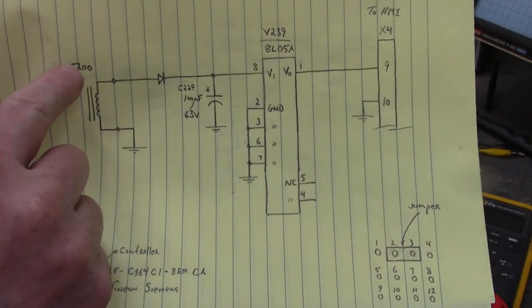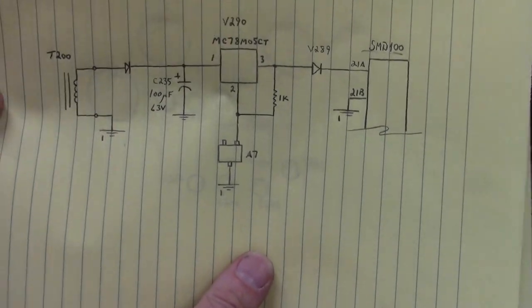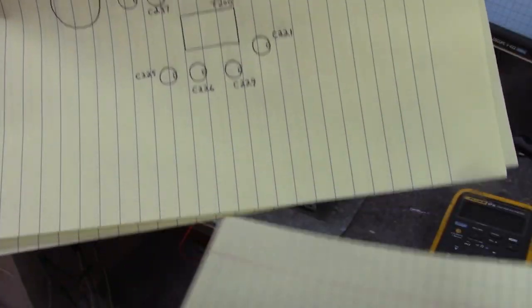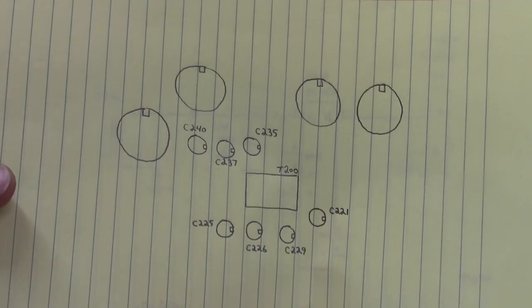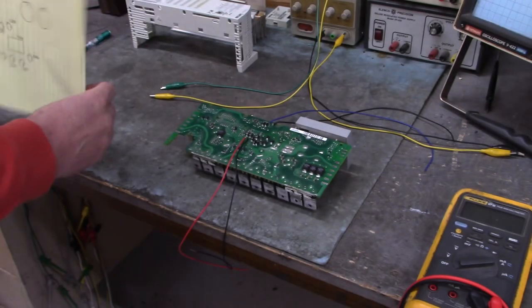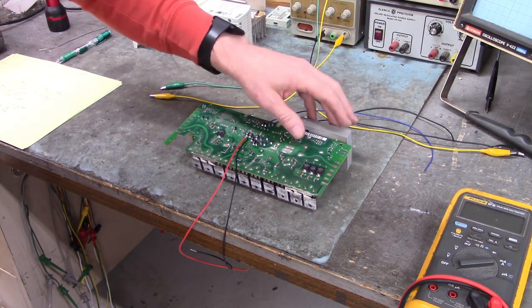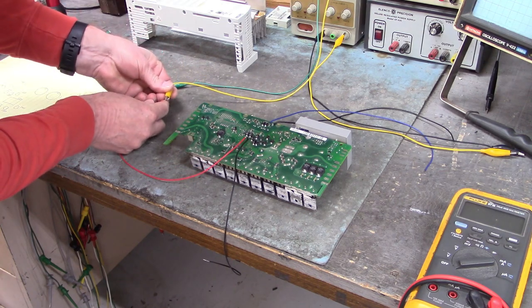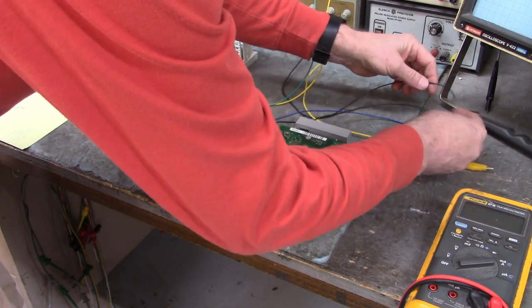I'll put my drawings up at the end of the video, but here's the circuit that powers up the panel or the lecom where we're going to pull the parameters out of that drive. And here is the power supply circuit that powers up the control. Here is a picture of the capacitors and I'll show you which ones that you want to tack on to with your wires and soldering iron at the end of the video. We'll talk about all of that. So I've got both power supplies set to 10 volts. This one down here is going to power up the panel, this one up here is going to power up the control. So the red wire, we want to put plus 10 volts on the black wire ground. I'm going to do the same thing on the operator panel side.